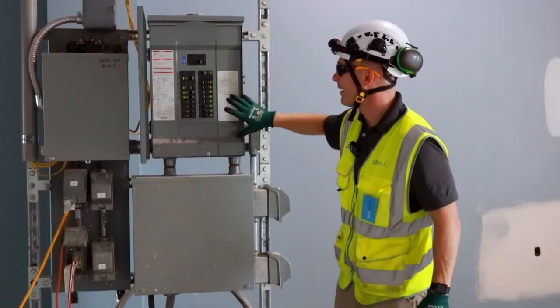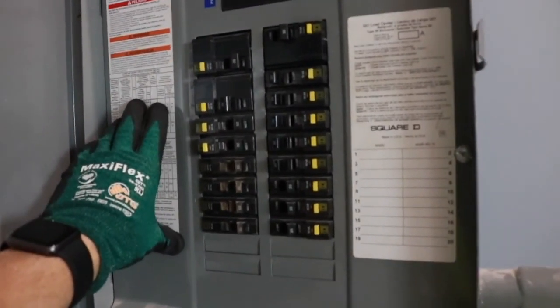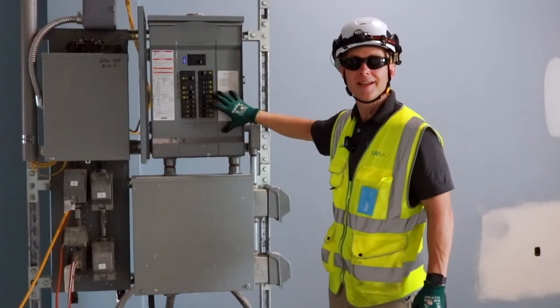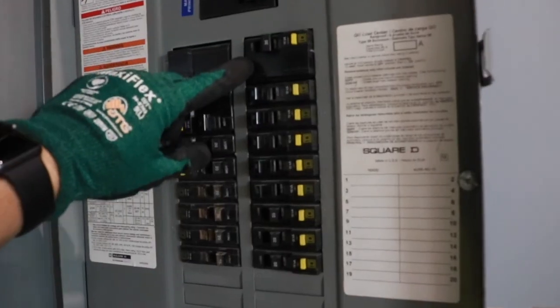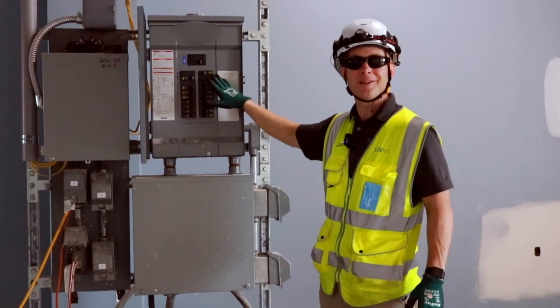Practice four, they have a dead front cover protecting anyone from accidental contact to the insides of this panel. Practice five, they've installed blanks to protect the knockouts from accidental exposure to the inside of the panel.